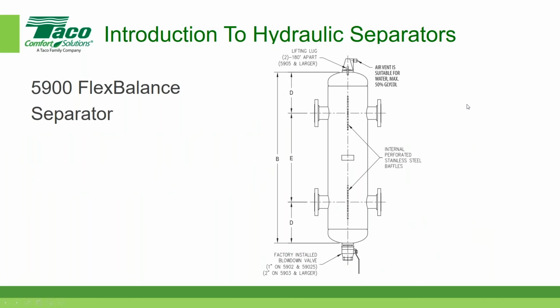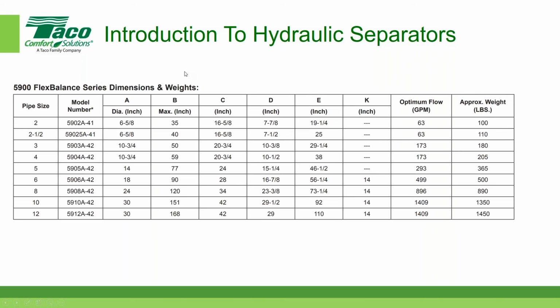So now let's talk about, I throw this in here because similar to what I hand sketched before, I want everyone to realize that when it comes to a pre-engineered device, all of these dimensions are critical. The overall height, the distance between the connections and the top and the connections and the bottom. Now the diameter is also important, and the flange size connection, which we'll get to in a moment. So all of these are important relative to a pre-engineered device. All right. So this little chart is copied right from the Flex Balance hydraulic separator catalog, and it's actually a sizing chart.